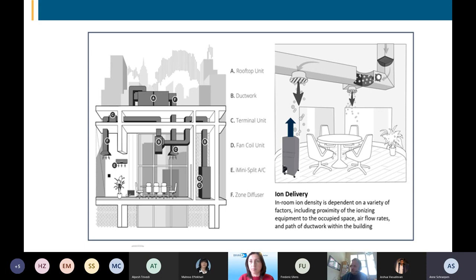You may see a very simple, fundamental installation, for example, installed inside a HEPA filtration machine, such as I show here, that might run under $1,000 installed. Depending on where you put the device and what type it is in the system, the prices would differ based on size, type and application. But it doesn't necessarily have to be overly expensive from a standpoint of first cost and operational cost. There are manufacturers that have ionization technology that requires no replacement parts and no cleaning. They're auto-cleaning, so its first cost is basically its life cycle cost. And typically electrical consumption is in the range of 15 watts or less per device.